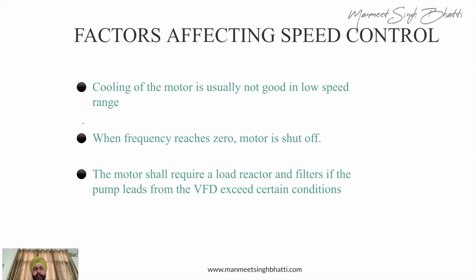So you have to be very careful that wherever you are going to use these VFDs, you should have proper ventilation. Or in case the VFD speeds are going very low, like around 20% or 30% of their rated speeds, it's always better to provide an external cooling fan outside that motor so that the motor remains cool. So that is a very important factor whenever you are using a VFD with a motor. Be sure how low you can get the RPM. So if your RPM is 20 to 30% of the actual rated speed, better to put in an extra fan for the cooling of that motor.